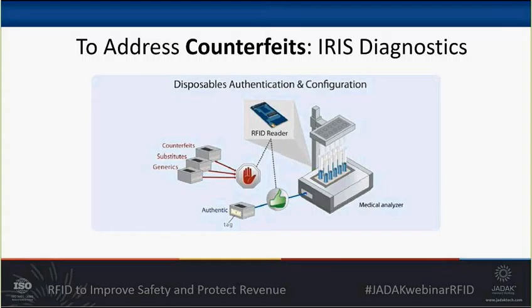So the reader can verify that there's a tag on the reagent, verify that it's authentic, meaning that it came from the correct manufacturer, and that it's not a low-cost competitor, it's not a counterfeit, it's not any kind of generic. And then we can also verify that it's not expired, and we can verify that it's the correct reagent for the test that's being run. So by using RFID, Iris can actually stop counterfeiting, and then they can actually also take advantage of some other benefits, like preventing the use of expired products, or making sure that the system is automatically set up with the correct reagent. So they can take advantage of some other benefits intrinsic to RFID.